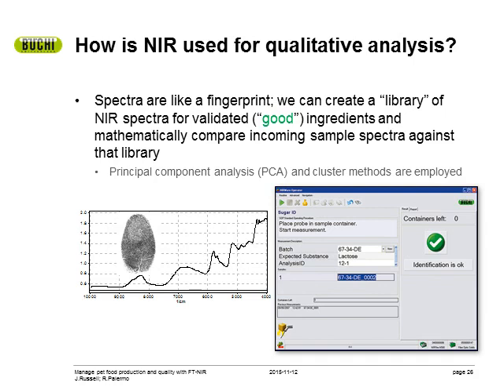So how does NIR work to qualify raw materials? You can think of each NIR spectrum you collect as a fingerprint. Samples that are of the same identity and quality will have nearly identical fingerprints, so when an operator collects their spectra, he will get the pass test result. If, however, the sample has different physical or chemical characteristics, the test will fail. The identity test is the result of some mathematical operations happening in the background within the software, specifically principal component cluster analysis.